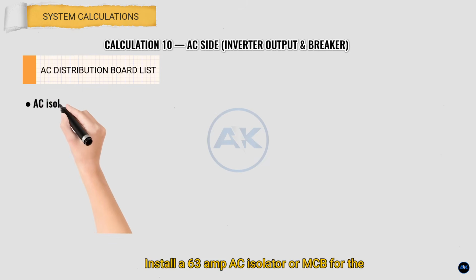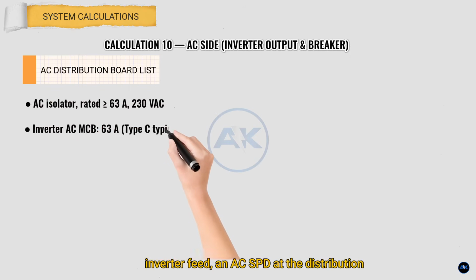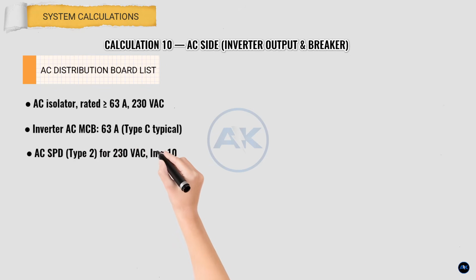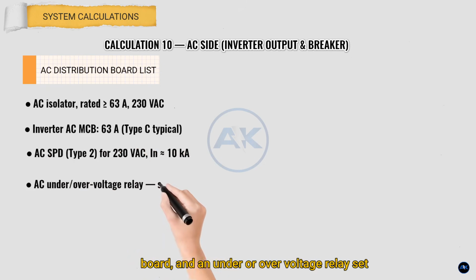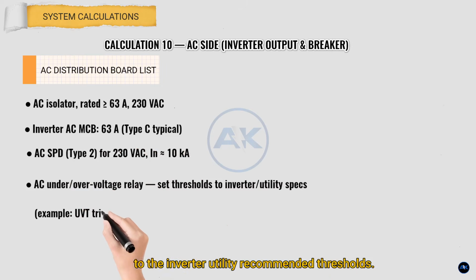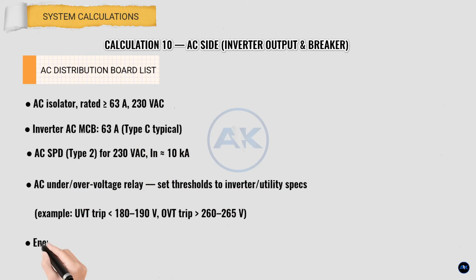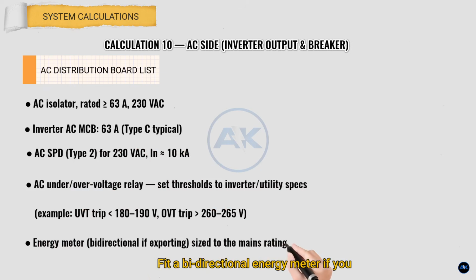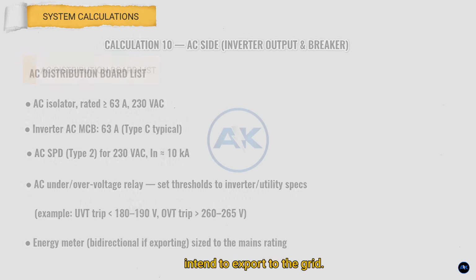Install a 63 amp AC isolator or MCB for the inverter feed, an AC SPD at the distribution board, and an under or over voltage relay set to the inverter utility recommended thresholds. Fit a bidirectional energy meter if you intend to export to the grid.